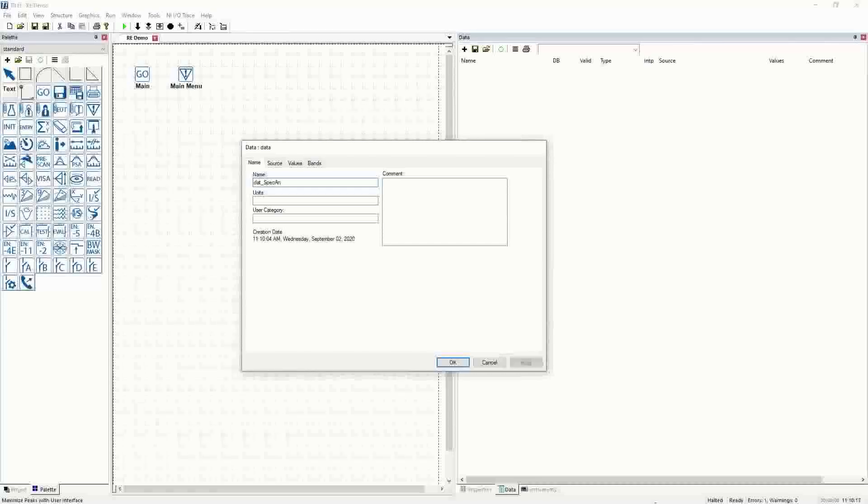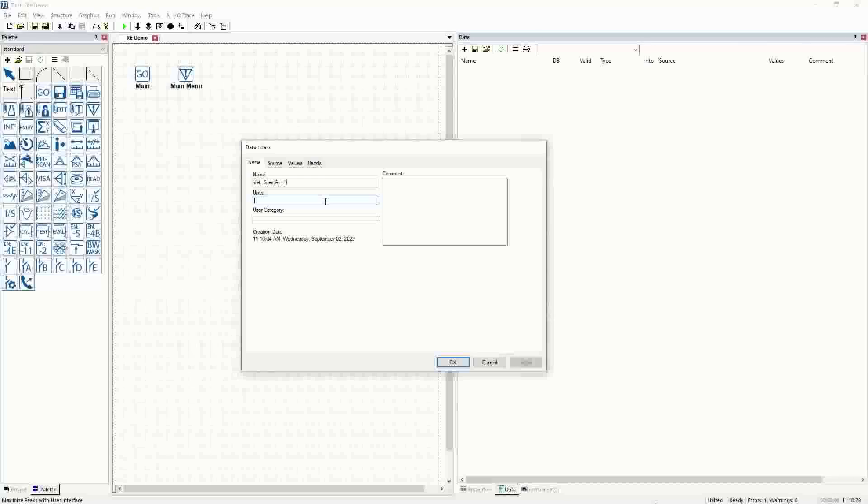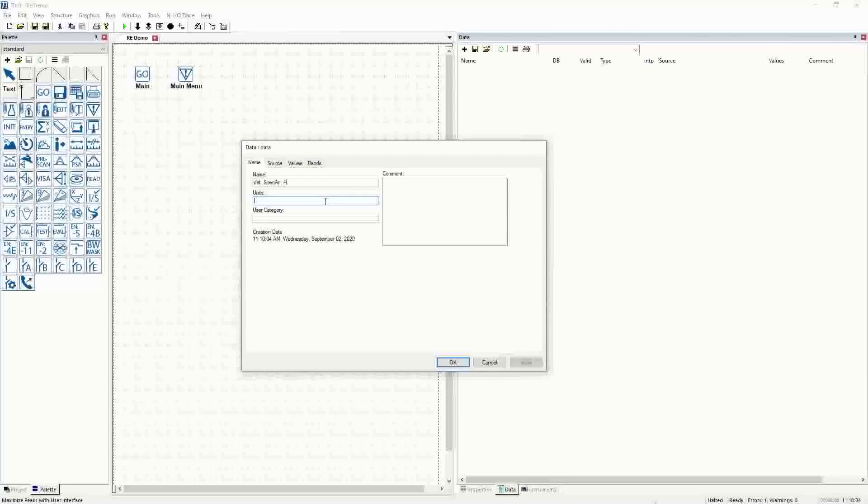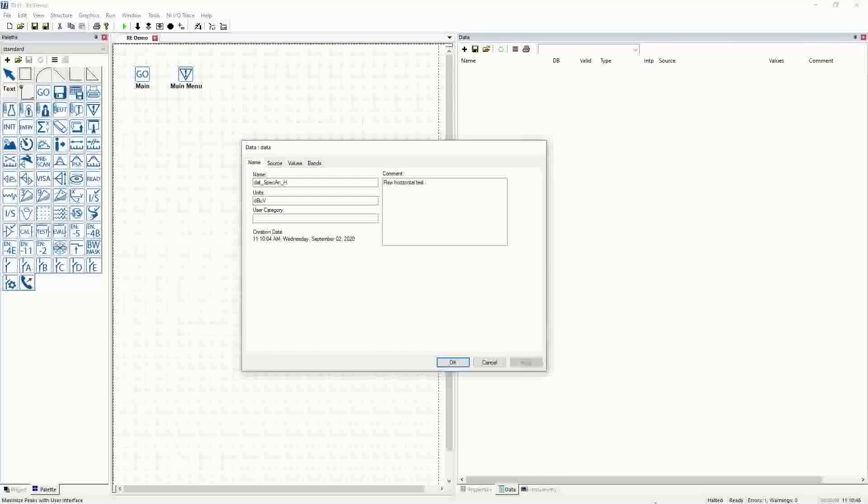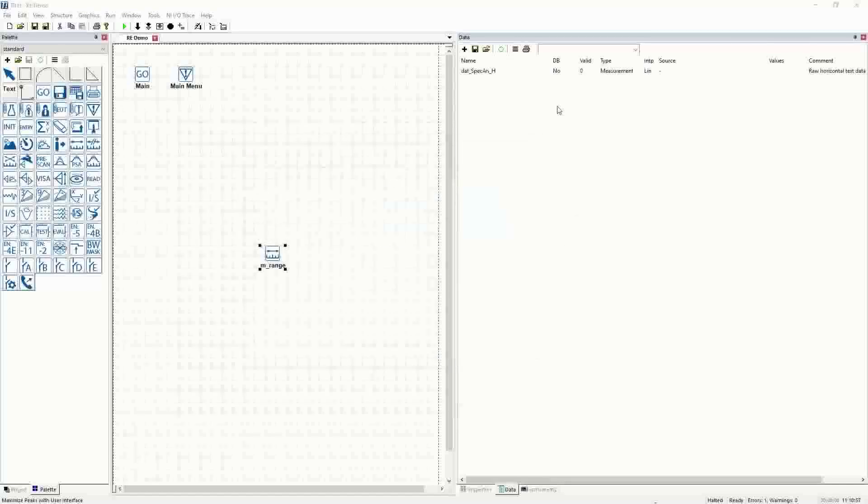We'll go into the data tab first and add a data item, which we reviewed previously. I'm going to call this dat_specan. Since we're going to do a radiated emissions profile, vertical and horizontal, we'll begin with the end in mind and call it specan_H for horizontal. The other boxes here are user boxes - you don't have to fill them in, but they're very helpful. When you read the spectrum analyzer, it's going to give you back dB microvolts, and this element is the raw horizontal test data. When I say raw, I mean it hasn't had cable losses or antenna factors applied - it's literally the raw numbers out of the instrument. We'll save that.